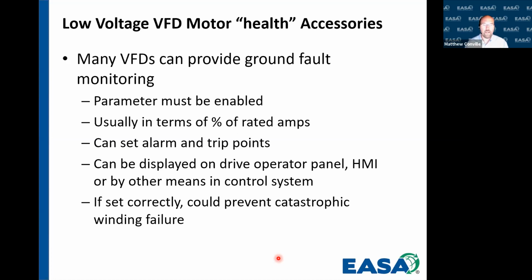We can also display these values on the drive operator panel. You can display it on an HMI, or human machine interface, or by any other means in the control system. If we've set it correctly, we can actually prevent catastrophic winding failure, which is pretty neat. The caveat here, one of the things we have to be careful about, is if we set our ground fault monitoring so low, if we have some sort of transient event, we might get nuisance trips. So what I used to do is I would set what I would think to be a conservative value for a trip on the ground fault, and then I would set an alarm at what I thought would be something good for that application. And we would check to see how many different alarms we got over time. If that alarm seemed to be set appropriately, then we would just set the trip point somewhere between 10 and 20% higher than that.